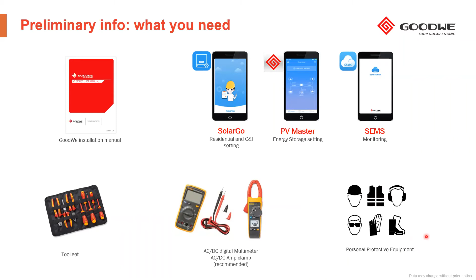You will need, of course, during installation, a tool set, whatever you need, plus a digital multimeter and amp clamp. I personally recommend an amp clamp because during commissioning you can check the PV system under operation, and it's very useful to identify potential mistakes or errors. And of course, personal protective equipment following local regulation.